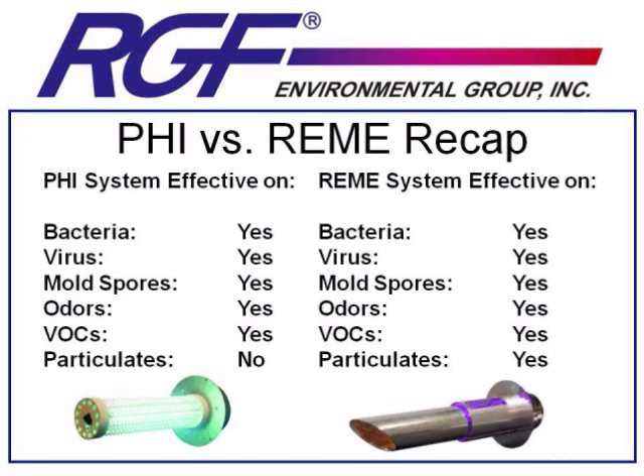To recap the differences: the PHI system is effective on microbes and gases — bacteria, viruses, mold spores, odors, and VOCs — but not on particulates like dust, dander, and pollen. The REME system is effective on all the same things as PHI, and in addition helps existing filter equipment better remove particulates by increasing their size. If there's someone smoking inside, a high level of particulates, or someone with allergy issues, the REME will be a better fit. If your main concern is mold, microbe growth, or odors, the PHI system will be a slightly less expensive option.